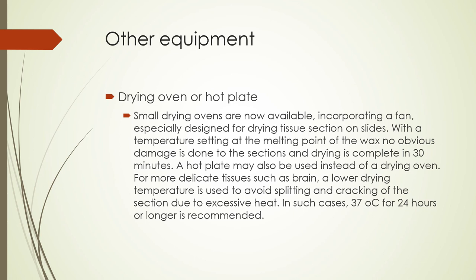Next, we have the drying oven or hot plate. Small drying ovens incorporating a fan are specially designed for drying tissue sections on glass slides. With the temperature set at the melting point of the wax, no obvious damage is done to sections and drying is complete in 30 minutes. For the flotation bath it's 10°C below the melting point, but for the drying oven or hot plate it is set at the melting point of the wax. A hot plate may also be used instead. For more delicate tissues such as brain, a lower drying temperature must be used to avoid splitting — 37 degrees Celsius for 24 hours or longer is recommended, because brain tissue is very delicate.